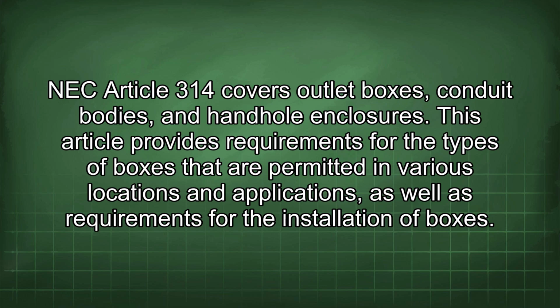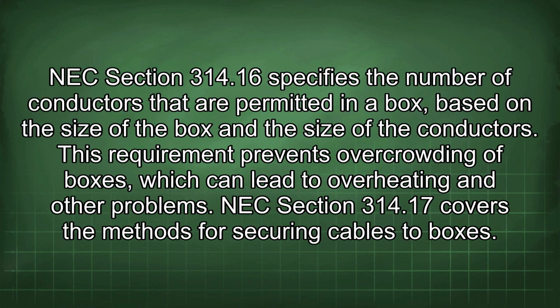This article provides requirements for the types of boxes that are permitted in various locations and applications, as well as requirements for the installation of boxes. NEC Section 314.16 specifies the number of conductors that are permitted in a box, based on the size of the box and the size of the conductors. This requirement prevents overcrowding of boxes, which can lead to overheating and other problems.